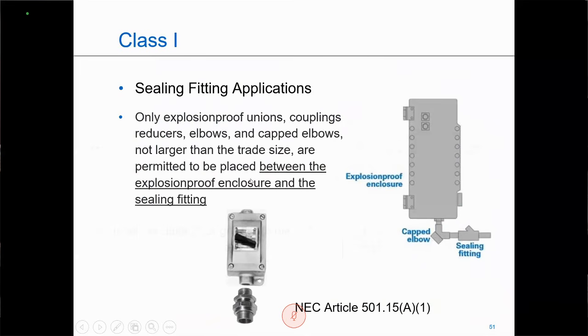Also, if you have units that have feed-through hubs and you didn't have unions, the only way you were going to be able to take that unit off the wall or out of that conduit system would be to cut the conduit. But by having a union at the bottom and a union at the top, each end, you disconnect your conductors, unscrew each union, and then simply just pull the product away from the conduit, and then you repair or replace it.